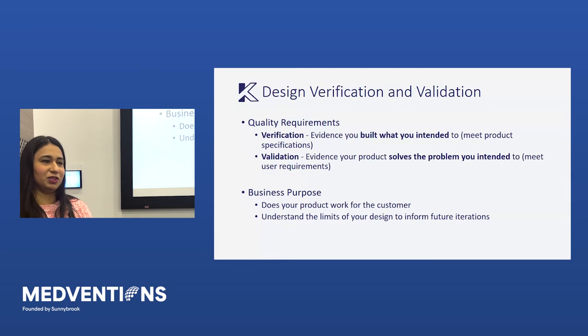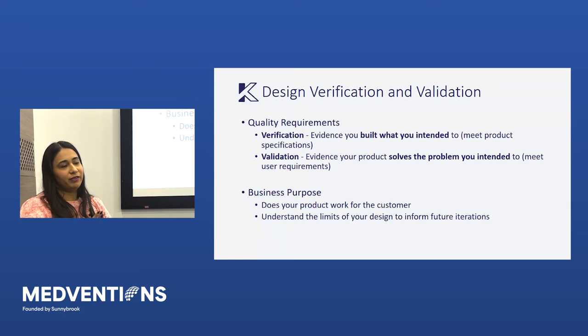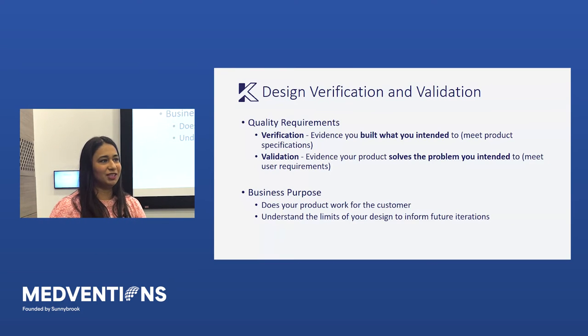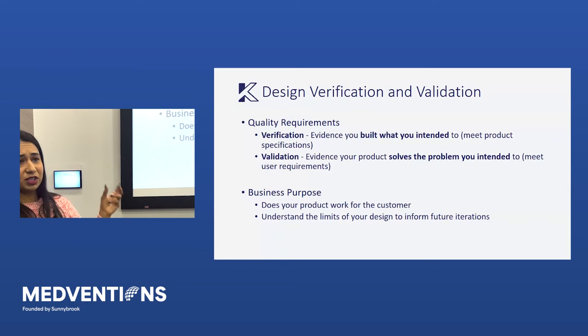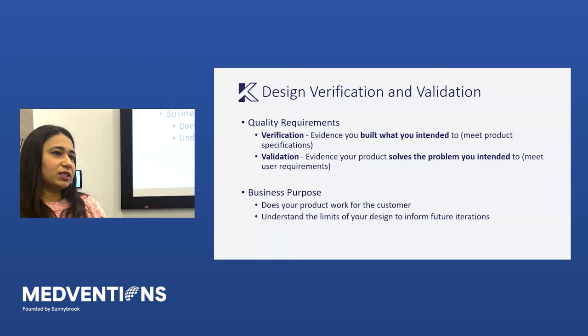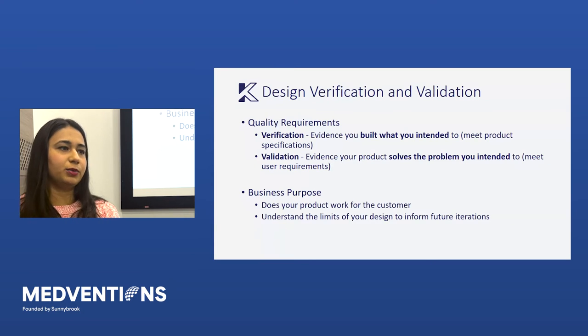From a business perspective, you really should be testing product before it goes to market — this makes sure your product is going to work in the field. No V&V goes smoothly despite bench testing during builds. What you're really doing through V&V — even if you accept the design and send it to market — is learning a lot more about your product. You may identify a set of failures that aren't safety-related but will cause non-safety faults and field issues. You generally end up with a hit list of sustaining changes to make after launch. It's really helpful for understanding your product limitations and knowing what issues you're going to have in the field, what's going to be returned, and how to plan for that.